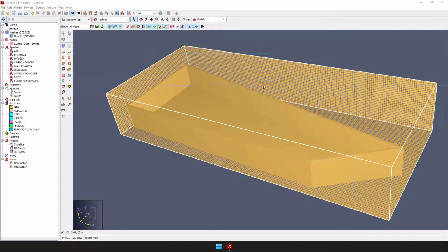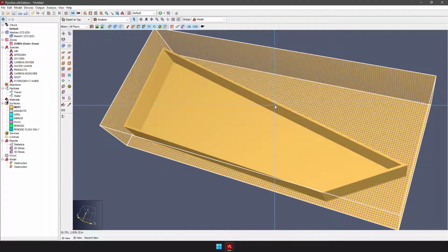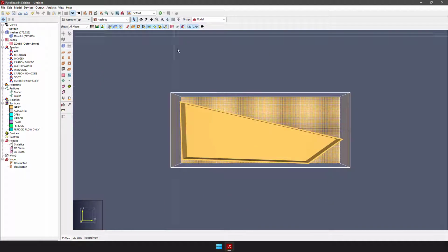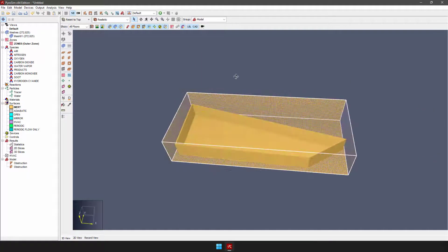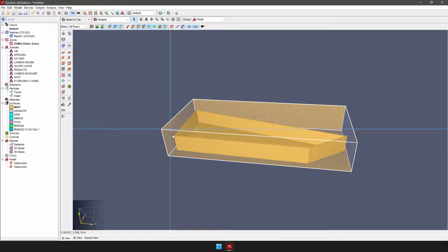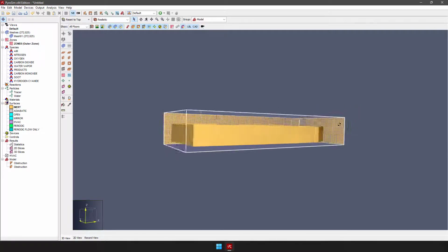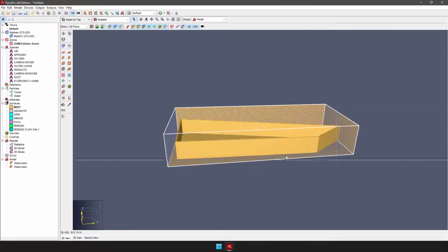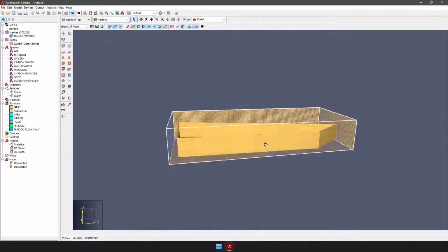We're starting with this unusually shaped model, and we've got to fit this shape within a rectangular or rectilinear mesh, right? We could break this up into smaller meshes, but regardless, you're going to end up with some amount of space outside of this volume. We only want to compute what's going on inside the volume of the building and not everything everywhere. You can see here that this mesh is not very efficient. I'm starting out with like 272,000 cells, but it extends way past the edges, the top and the bottom of this domain.